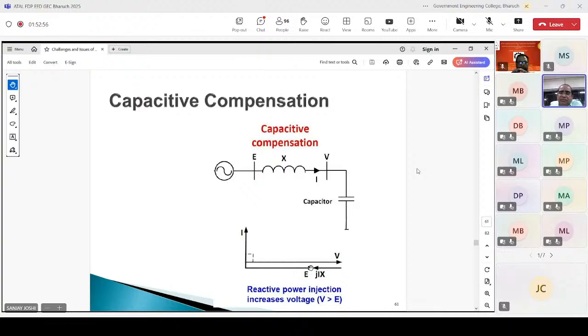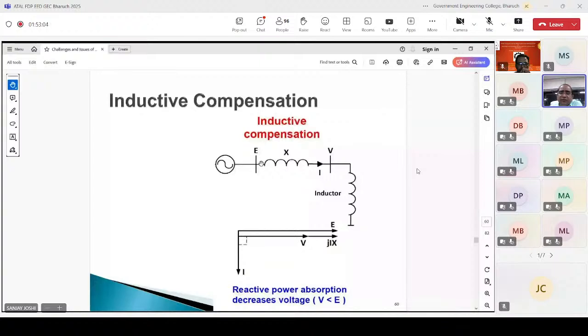So what is proved here is that for capacitor compensation, voltage rises and becomes more than E, while for inductive, the voltage at this bus is less than E. So in a weak system, that is high X, greater changes in voltage occur for the same reactive power injection or absorption.